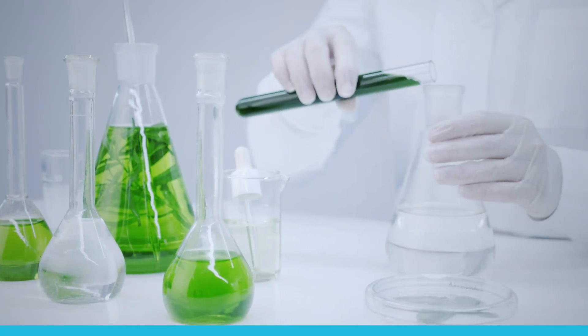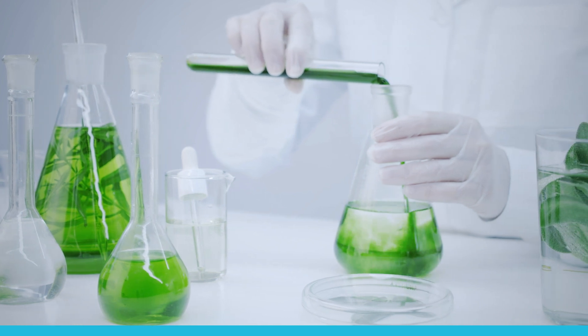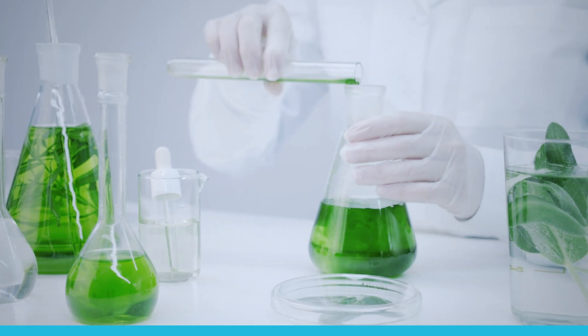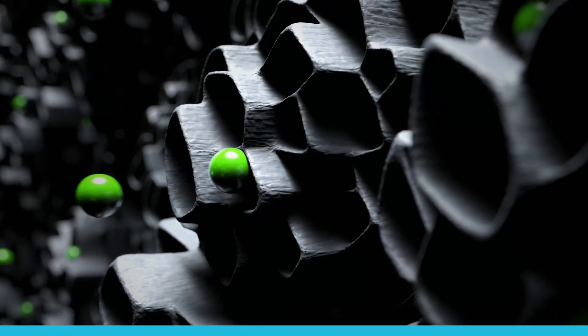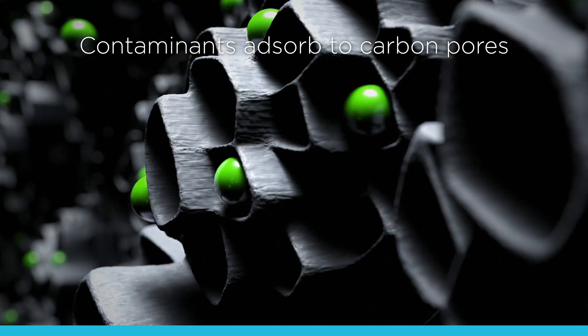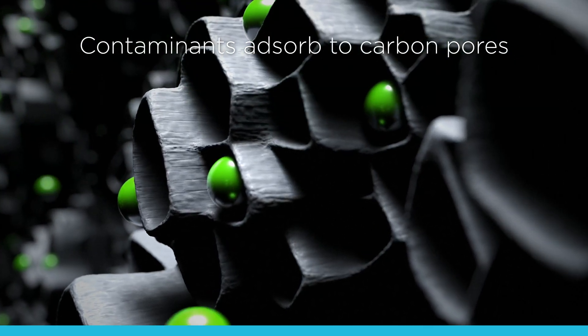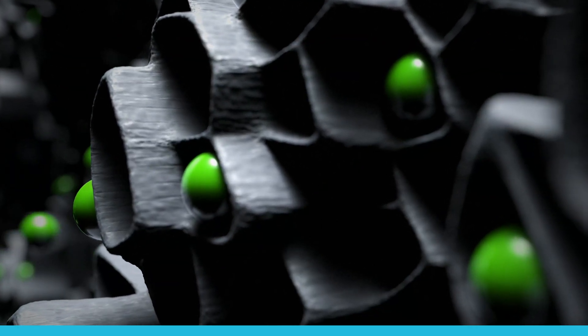The media inside the vessels is determined by the specific chemistry of the water being treated. There are many different types of carbons and resins. Every spoonful of activated carbon has the surface area of a football field. Contaminants like PFAS travel inside the carbon granule and are adsorbed inside the pores of the media structure.